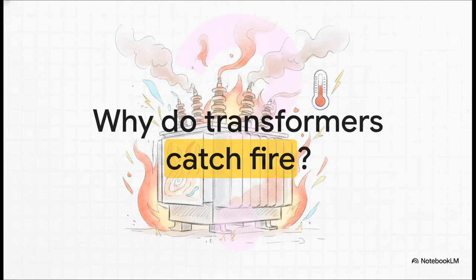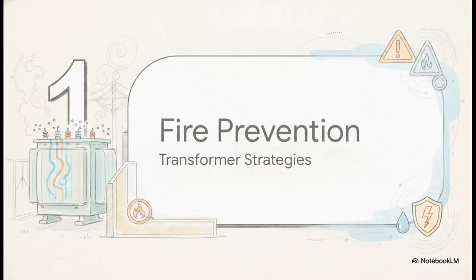Okay, we're starting with literally the highest stakes imaginable in the substation: fires. I mean, think about it. A transformer is essentially just a massive metal box filled with copper windings and, oh yeah, highly flammable cooling oil, all operating under immense electrical stress. So when insulation fails, or if a massive electrical arc happens, that oil can ignite. You get a rapid spike in temperature combined with high voltage, and it is just a perfect recipe for a catastrophic physical failure. Which brings us to Section 1, Transformer Fire Prevention Strategies.